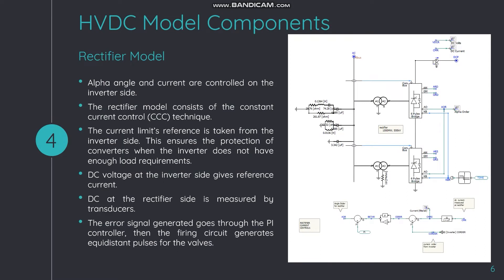The first component is the rectifier model. The rectifier model consists of the constant current control technique, CCC. The current limits reference is taken from the inverter side, which ensures protection of converters when the inverter does not have enough load. The DC voltage at the inverter side gives the reference current and the DC at the rectifier side is measured by transducers. The error signal is generated and goes through a PI controller, and then a firing circuit generates equidistant pulses for the valves, as shown in the figure on the right.